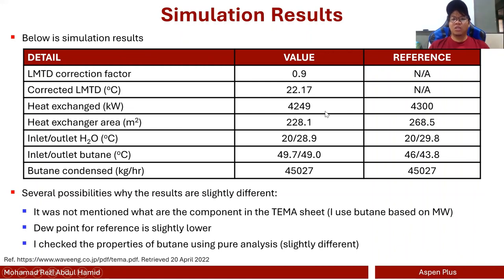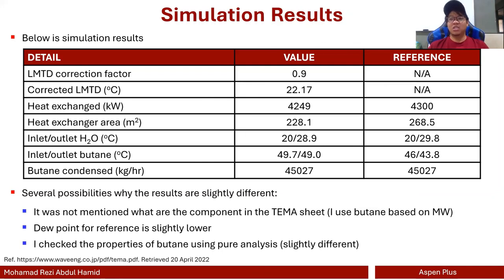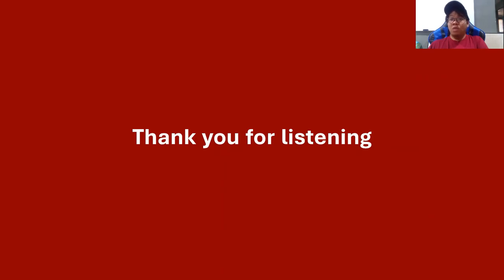Those are the factors contributing to the differences in heat exchanged and heat exchanger area. The LMTD correction factor was not specified in the datasheet because geometry wasn't provided. I did confirm that even though I chose butane, the thermophysical properties are slightly different — not because of an incorrect property method, but because the reference fluid is not explicitly identified. It's essentially an apples-to-oranges comparison, even though the properties are roughly similar. That's all for today — if you liked the video, give it a thumbs up and consider subscribing. I'll see you in the next video. Bye-bye, and happy Hari Raya!